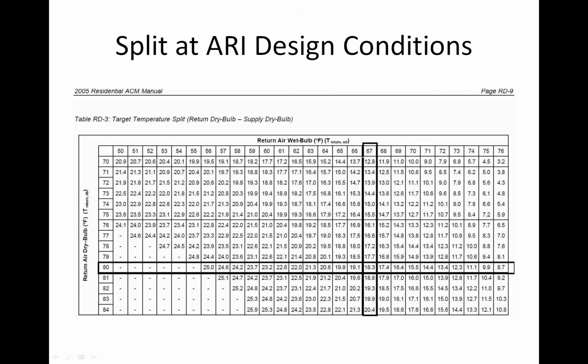So, where did my dad get that from? Well, some engineers sometime told my dad, yeah, about a 20-degree drop across the coil, because if the system, again, was designed to operate with a 67-degree return air wet bulb and 80 degrees outdoor air temperature, well, that comes out to about an 18-degree drop across the coil, right? Now, if we're talking 95 degrees, you can see that's increasing if we go out there, so it might be closer to 22 at 95. I just picked 80 on this.